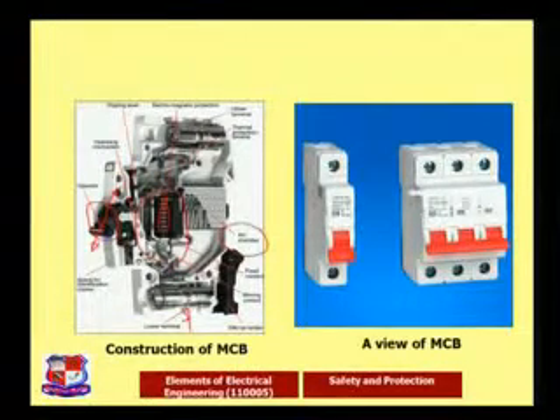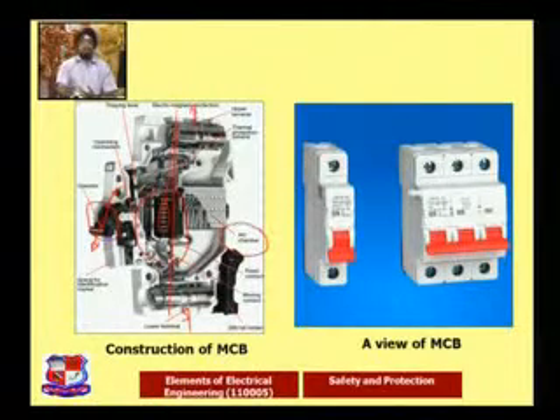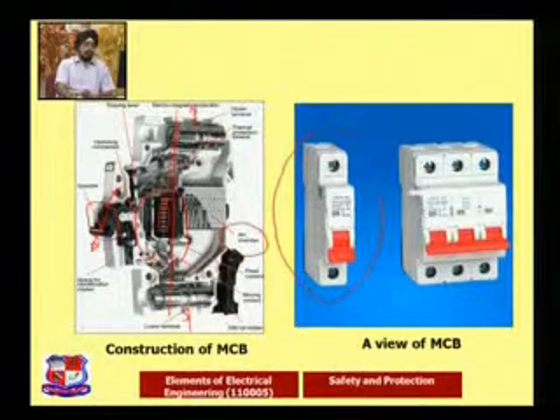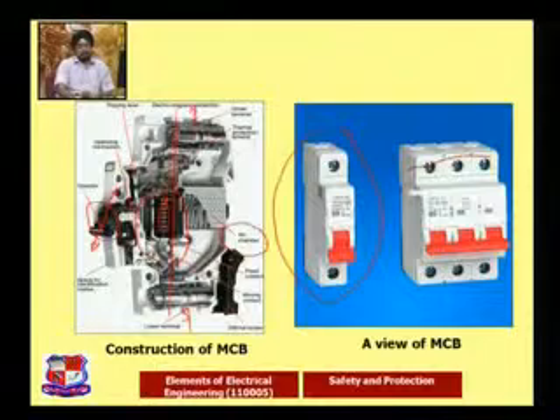Over here the lower terminals and upper terminals are there, meaning the incoming line and the outgoing lines. Again, all these mechanisms are connected in series, so current is never going to flow in an open circuit. That's why all this equipment is connected in series. As soon as the plunger strikes, this switch comes to the downward side and the circuit becomes open. The next view is of the MCB construction. The MCB is there: single phase is one pole, and a 3-pole circuit has one incoming line and outgoing line, 3-phase RYB. In that way we can see how the MCB is connected into the actual circuitry for protection purposes.